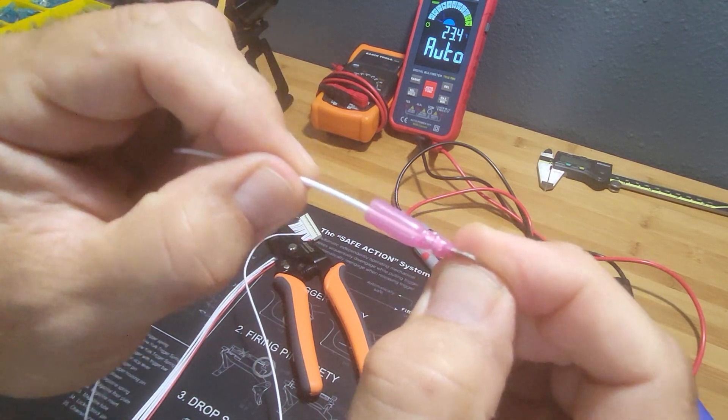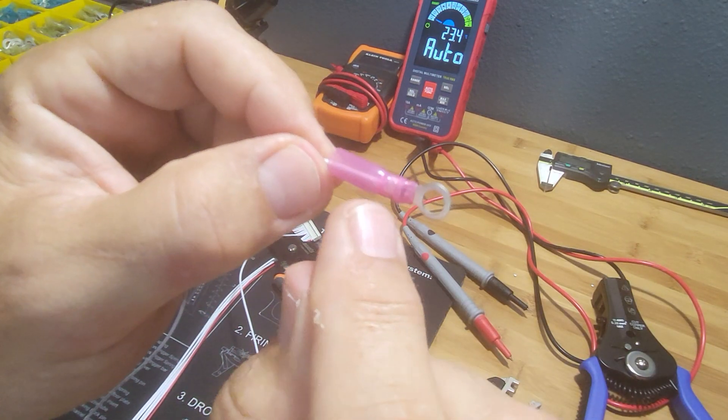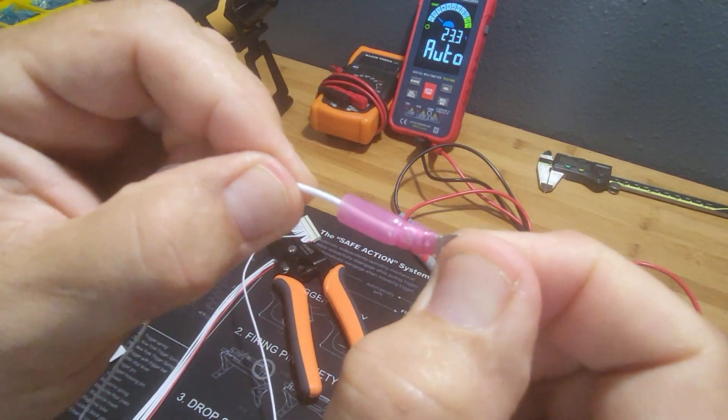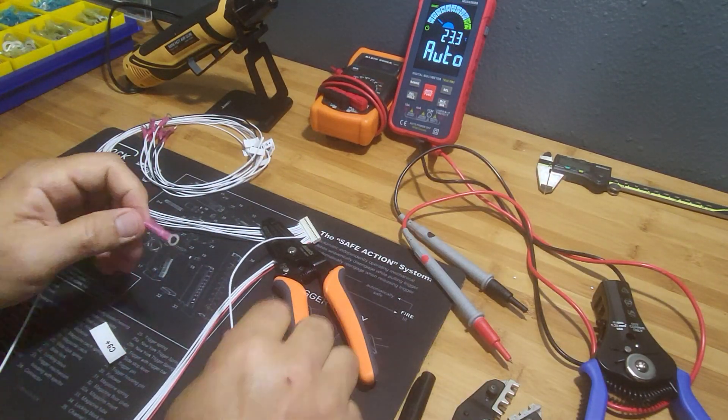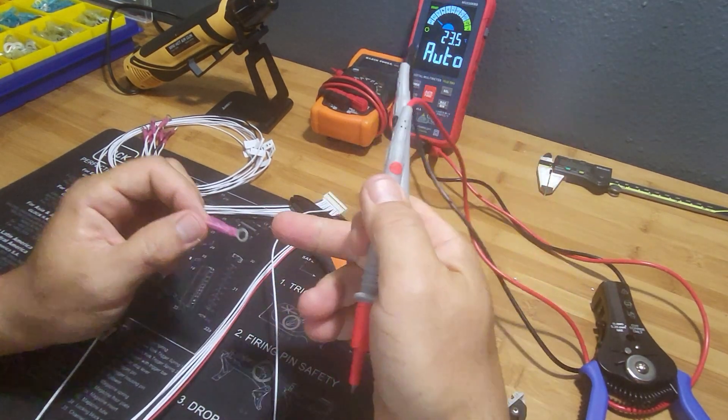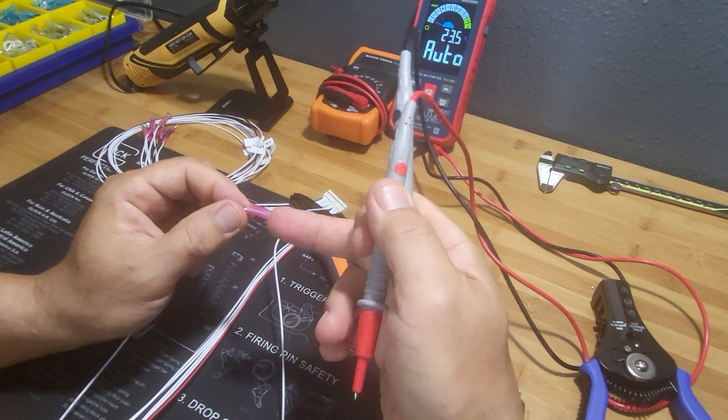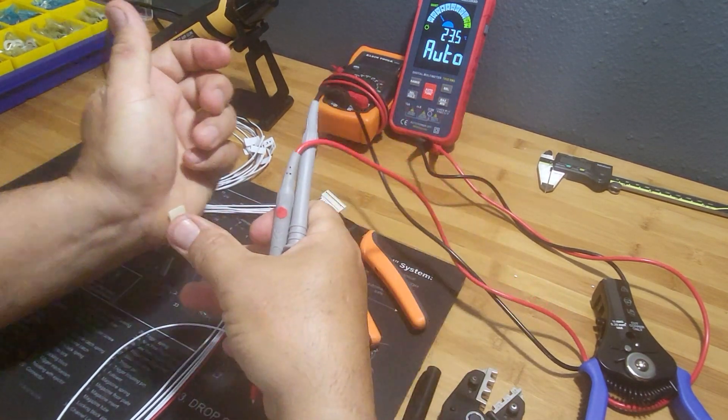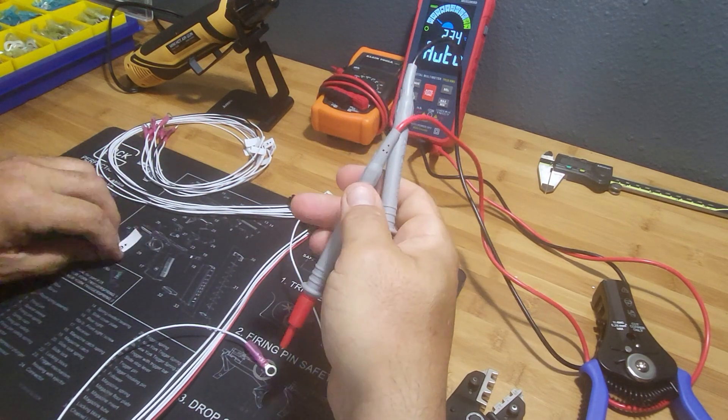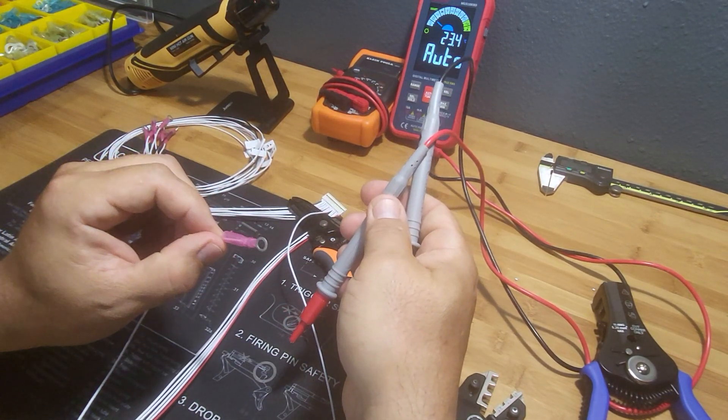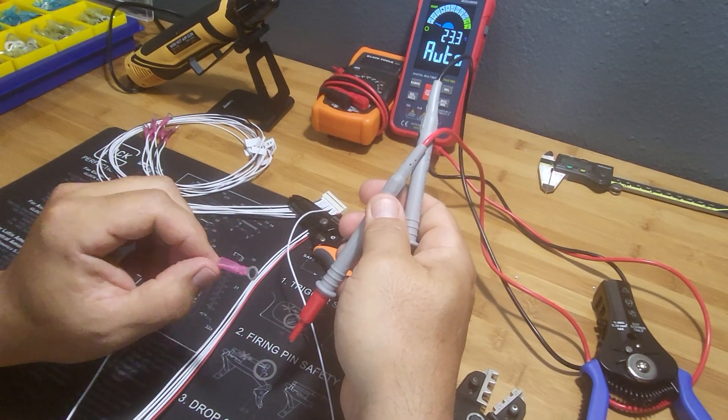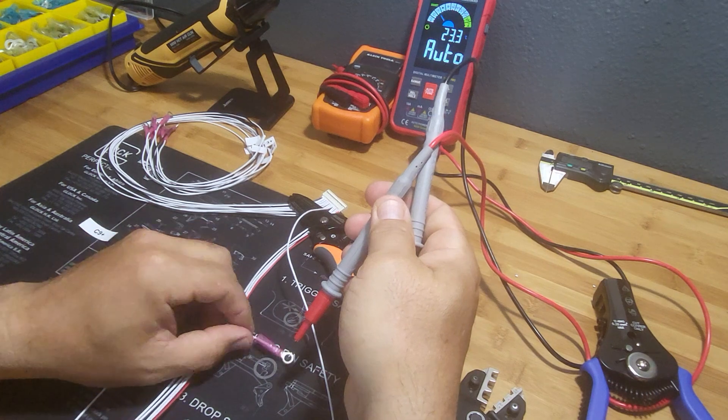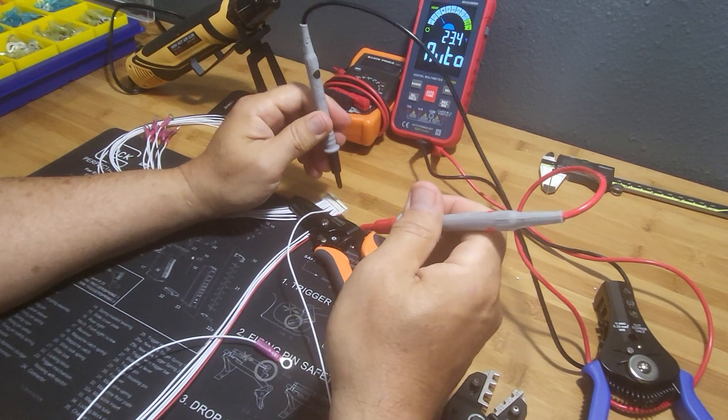If I look down into this, it looks like a good solid crimp down in there. I'll do a tug test, and even some people when they crimp on top of the insulation, they'll do the tug test and it's fine, but they're crimped on top of the insulation. Another way to avoid missing that error is if you're testing your batteries and you've got an issue and you don't know why - is it the crimp terminal, is it the lug not being torqued properly, is it the lug on the battery itself, or just the battery?